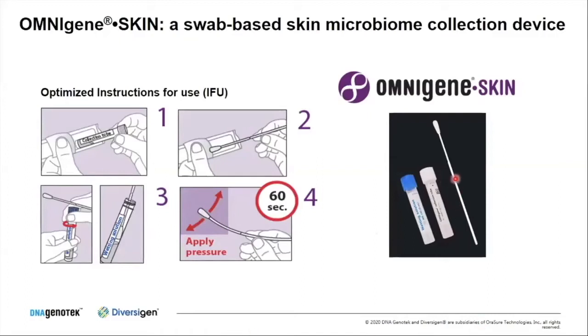We developed Omnigene Skin, a swab-based skin microbiome collection device. It's a very simple device consisting of a flock swab with a breakpoint, an Omnigene collection tube containing one milliliter of stabilization buffer, and a wetting solution used to moisten the swab prior to collection. Also included are our optimized instructions for use. We spent a lot of time developing those IFUs to ensure the end user collecting the sample at home would do as good a job as possible. The steps are simple: take out the tube and swab, dunk the swab in the wetting solution, then collect from the site of interest for 60 seconds while applying significant pressure to capture as many microbial cells as possible.